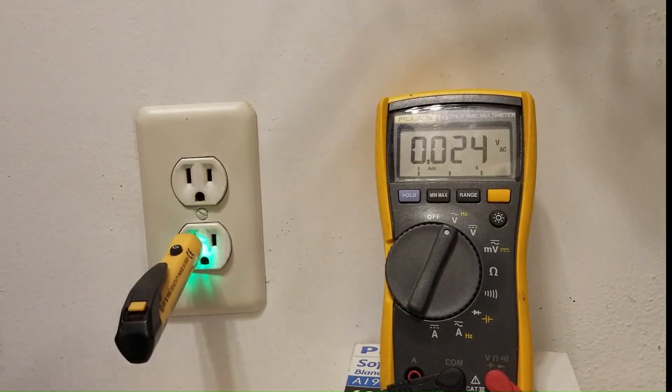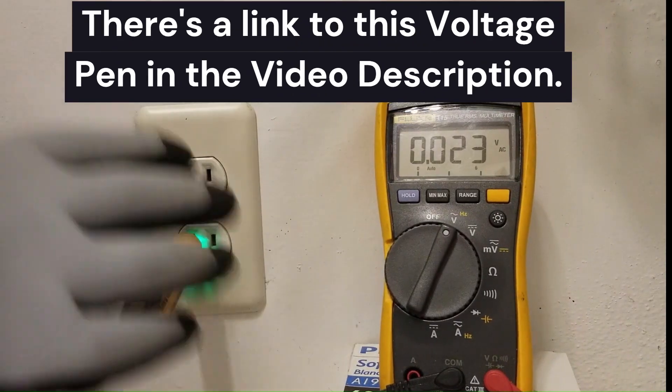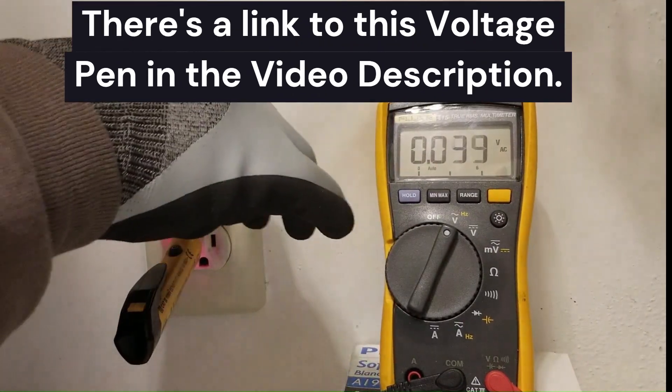So the voltage pen is indicating that neutral is getting pulled up to 120 volts when we plug this in.